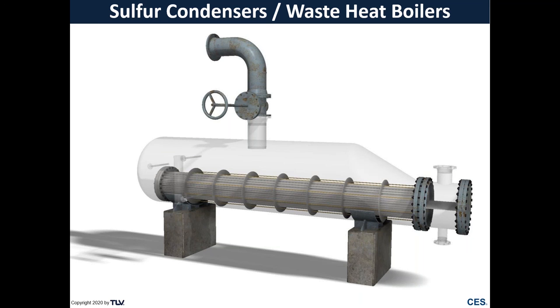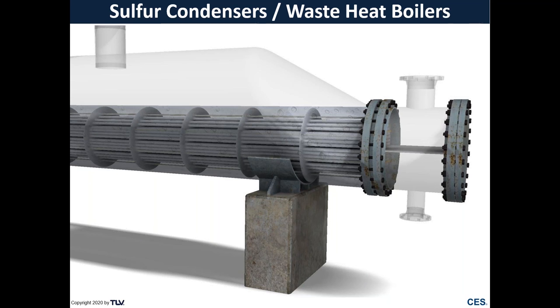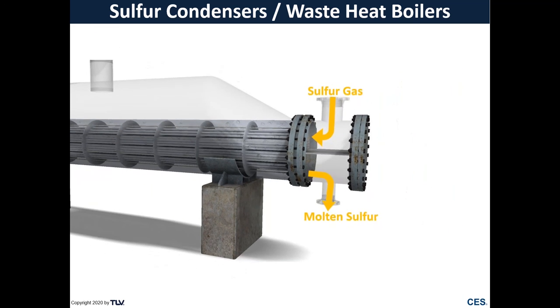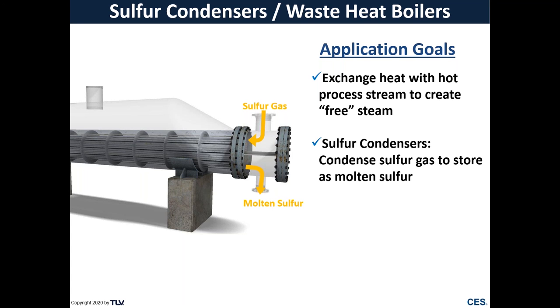And if we fill our condenser with boiler feed water, we can then condense the incoming hot sulfur gas that has just left the combustion process or the catalytic reactors. So the heat exchange allows for the creation of what is essentially free steam, since the heat exchange was from a process stream instead of burning fuel like natural gas at a standard fired boiler. The main job of the condenser is to help capture elemental sulfur for storage and later transport.